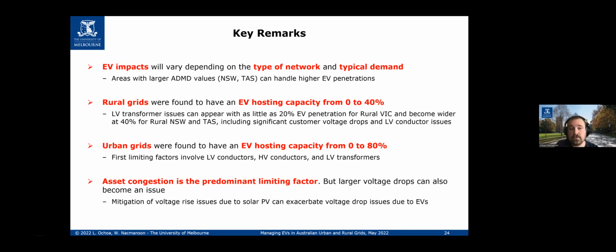Typically, we found rural networks can handle up to 40% EV penetration, some lower, before issues arise, while urban grids could go up to 80%. For urban feeders, asset congestion is probably the main issue, whereas for rural feeders, asset congestion is also a concern but voltages become more of an issue due to longer lines and impedance and voltage drop problems. But in general, asset congestion is the predominant limiting factor.